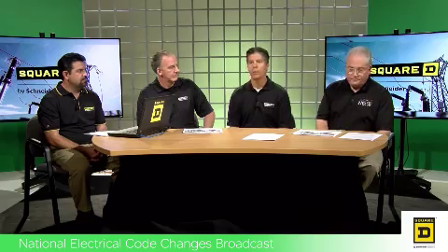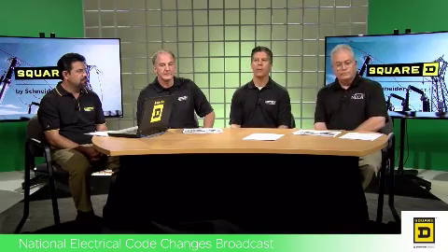Thank you both. From a safety perspective, before we leave this topic, it's important to recognize that although this label is on the service equipment and it includes the clearing time, the available short circuit current, this should not be used as the available incident energy or arc flash hazard determination for the service equipment. This marking is used for downstream equipment from the service equipment.